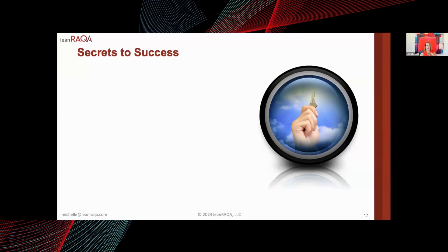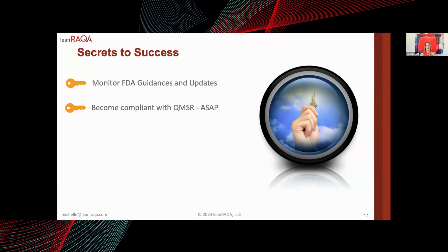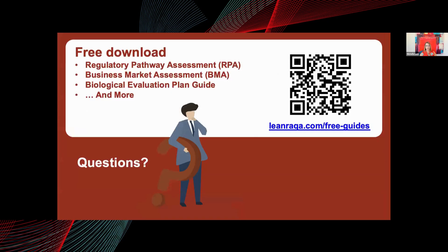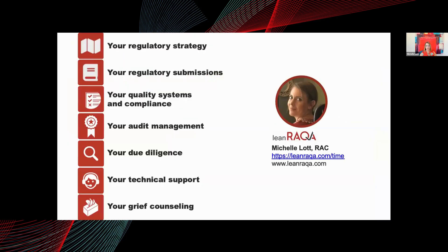For success in the US market: monitor FDA guidance documents, updates, and press releases to know their current thinking ahead of time. Become compliant with the Quality Management System Regulations (QMSR) as soon as possible — the clock is ticking with about a year and a half left to transition your QMS. Ensure you've selected the right regulatory pathway via the pre-submission process with the FDA, and use pre-submissions to understand FDA's position while leveraging the Breakthrough and STEP programs for expedited pathways. There are many resources on my website to help you navigate all of this.